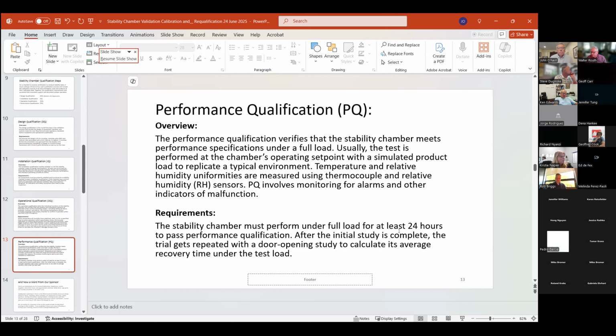So with the open door, I think it's pretty typical for a walk-in room. Most folks will do a 1 minute door opening. At the end of that 1 minute, obviously close the door and analyze the time that it actually takes to come back into spec. For reach-in, I think it's more commonplace to do like a 5 minute door open.